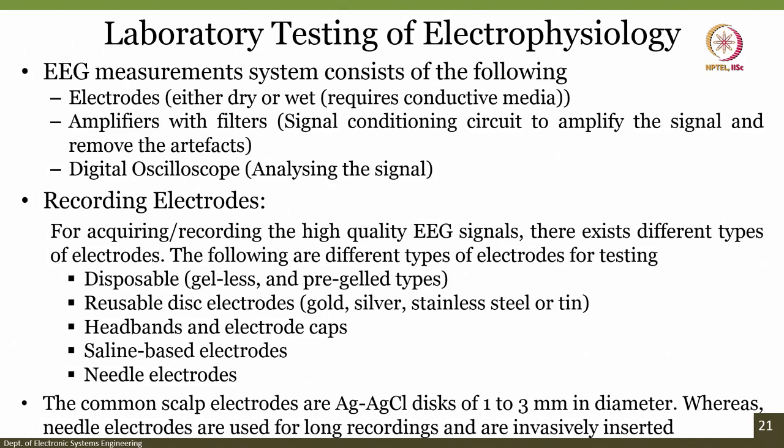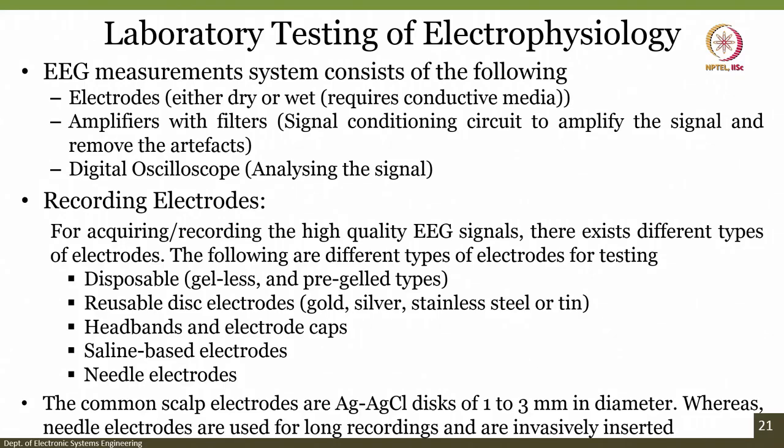If you want to do a laboratory testing of electrophysiology, the EEG measurement system consists of the following. First are electrodes — either dry or wet. Wet electrodes require a conductive media gel to improve the impedance. We also require amplifiers and filters: to amplify the signal because it is of very low amplitude, and to remove artifacts we require filters. Finally, you require a digital oscilloscope (DSO) for analyzing the signal in the laboratory environment.